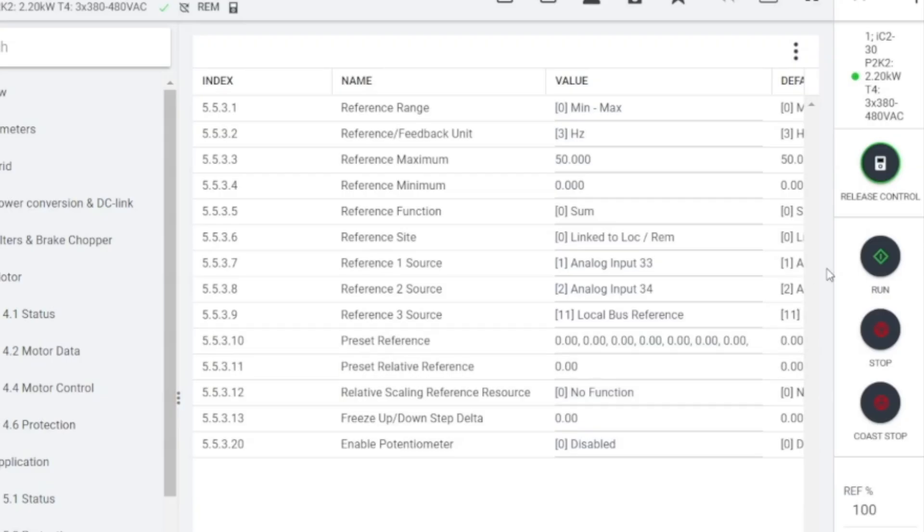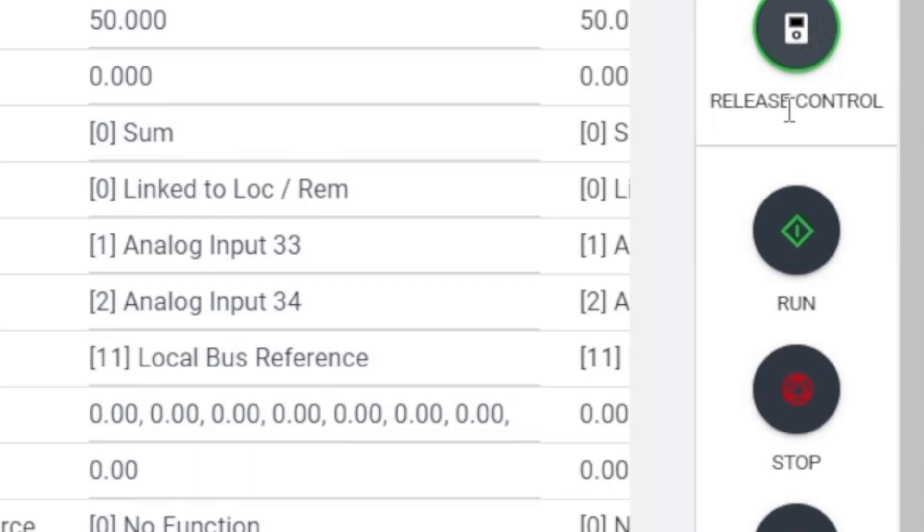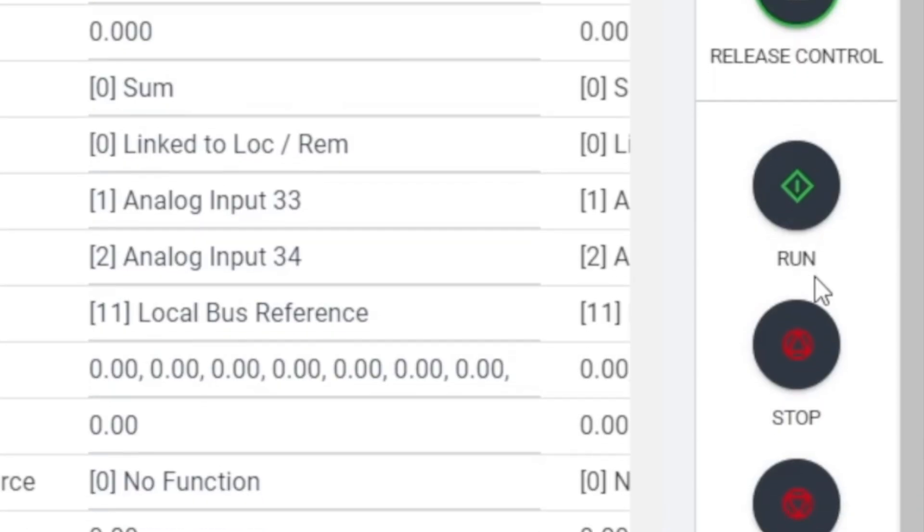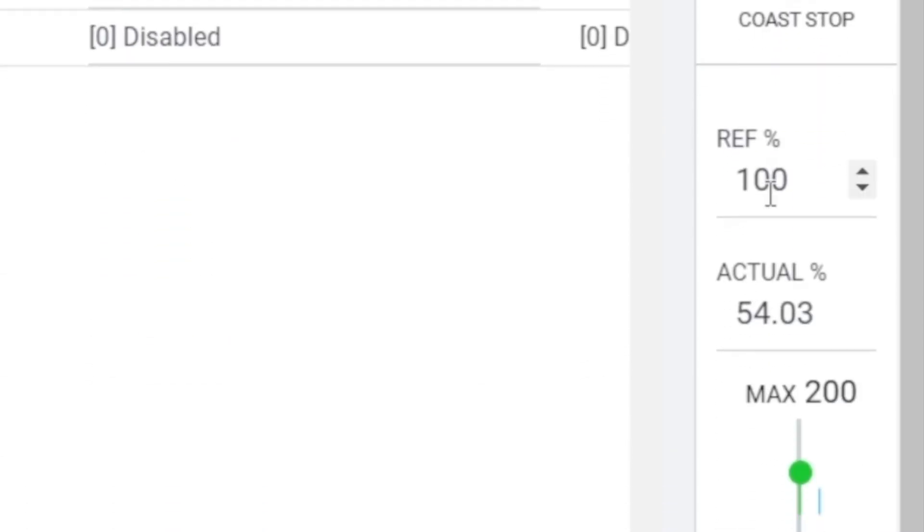To control the drive with MyDrive Insight, click the keyboard button in the upper right corner of the interface. After clicking Release Control, you can use Run, Stop, and Coast Stop buttons to control drive. The setting for the speed reference value can be modified by entering the reference percentage value or adjusting the slide rail below.